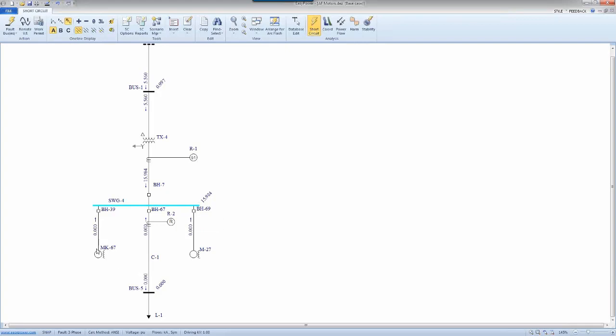And also I have a chance to look at the status of all protective devices and take those which are already tripped off, remove them, and make their contribution zero. So this iterative method, otherwise known as integrated method, will start looking at all these changes of the current over the time and calculates the current value, which happens to be a variable value. Now, you would expect that it's going to change over the time if you could plot it. So that's how much I cover it for now.